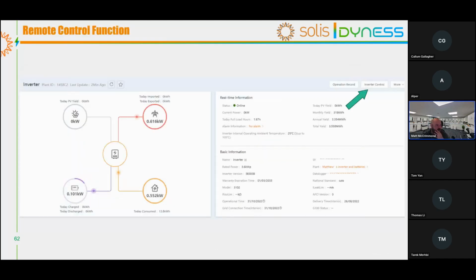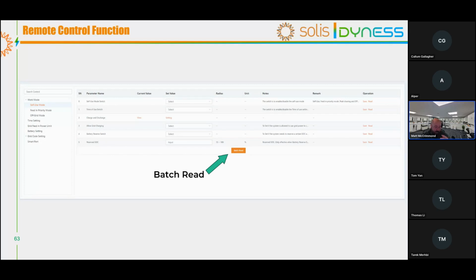So that's on the alarm page. In terms of the actual inverter, we have some stuff we can do remotely. So when you sign into the inverter, you go to the device tab, you select the inverter you want to control. Once you've selected the inverter you want, you can then select inverter control in the top right-hand corner. It will prompt you to put your password in again, and then just accept terms and conditions, because ultimately you're changing settings in the inverter, so we need to make the customer aware that if they change settings, then it's their liability to know what they're doing with it effectively. So nine times out of ten, the only thing they'll ever want to change is the time of use windows, so setting that up.